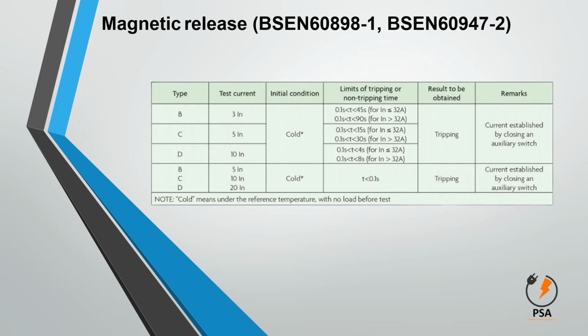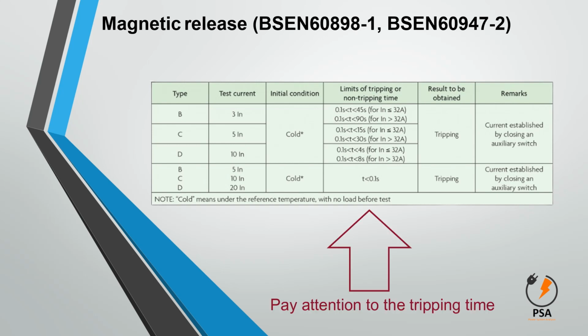There are many types of circuit breakers, while MCBs are classified into three major types according to their instantaneous tripping currents. They have an electromagnet with plunger and shunt for instantaneous tripping in case of short circuit. The BS EN 60898-1 distinguishes three different types, following the current for instantaneous release: Type B, C, D. The curves show the range of fault current at which a circuit breaker trips instantaneously.